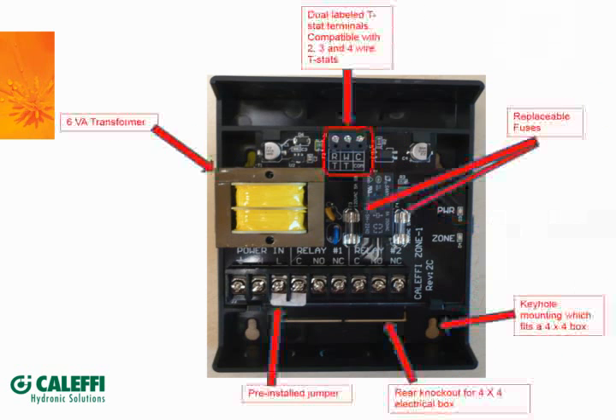So once you have it open, this is what the board looks like. We went with a black board with white text on it because it really jumps out at you in a dark boiler room. You can really see this well. We have a 6 VA transformer on board, and then we have our dual labeled T-stat terminals. Like we said, compatible with 2, 3, and 4-wire thermostats. So we dual labeled it. Just some guys are used to seeing the RWC, other guys are used to seeing TT. We also identified the common there.